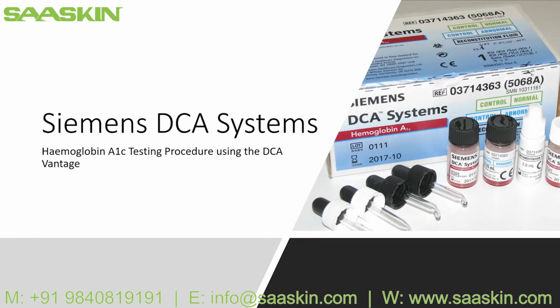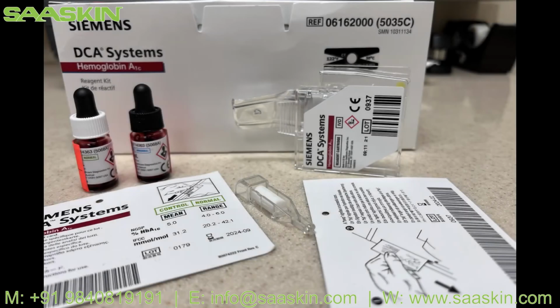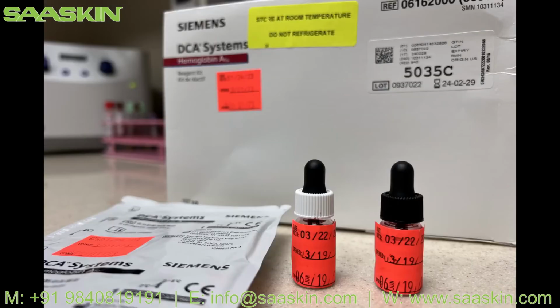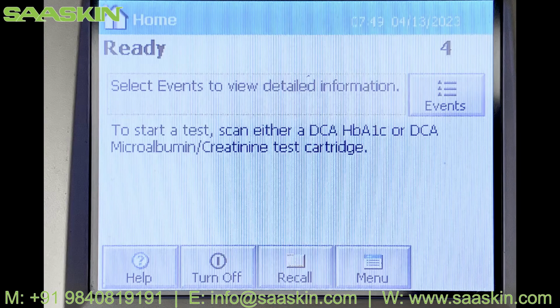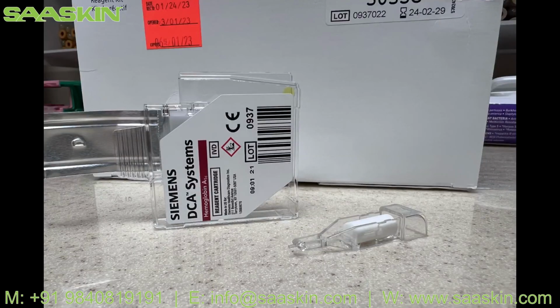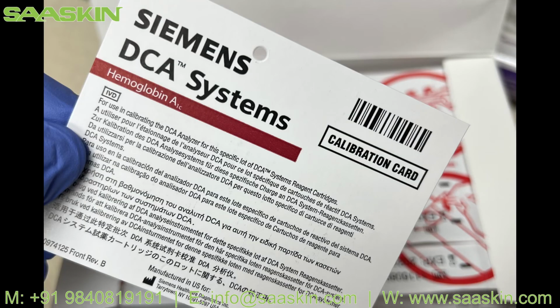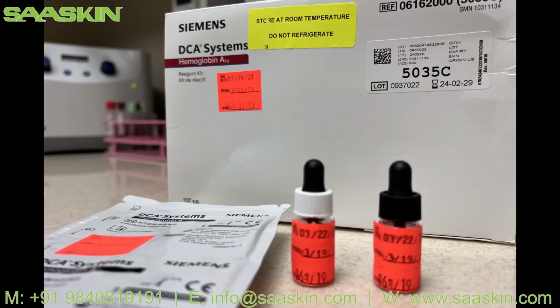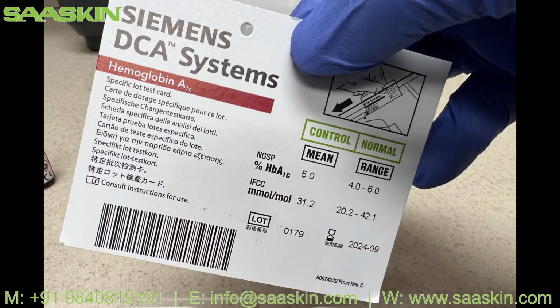Thank you for watching this instructional video for using the Siemens DCA Vantage. How to QC hemoglobin A1C. Check expiration date on the hemoglobin A1C controls and cartridge. Check hemoglobin A1C meter for readiness. Open the box, get a cartridge and a capillary collection device out. If it is a new cartridge box, scan the new calibration card. Stir controls before using. Scan the normal green side of the card.